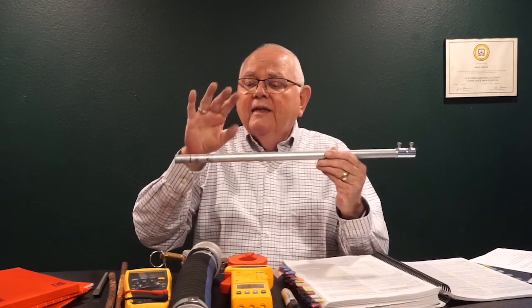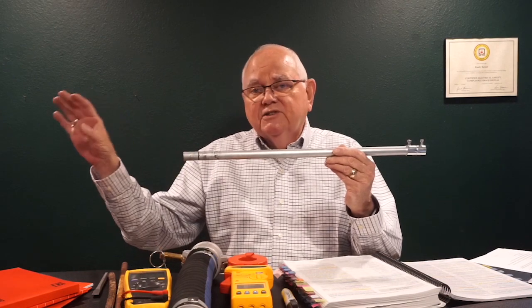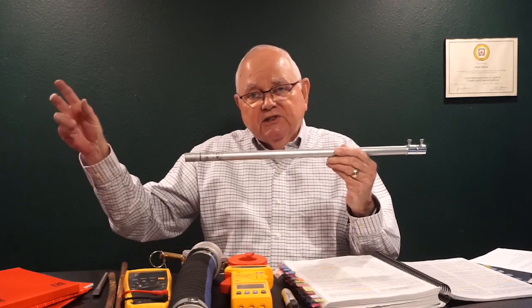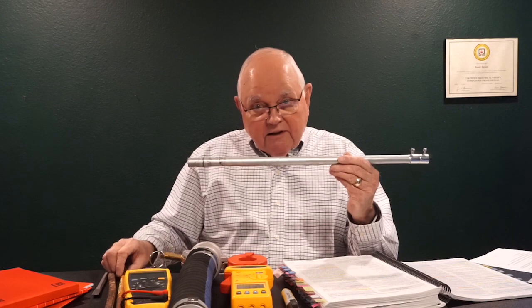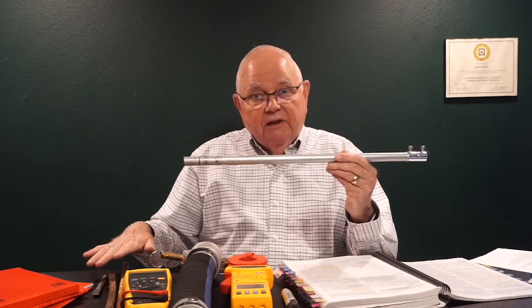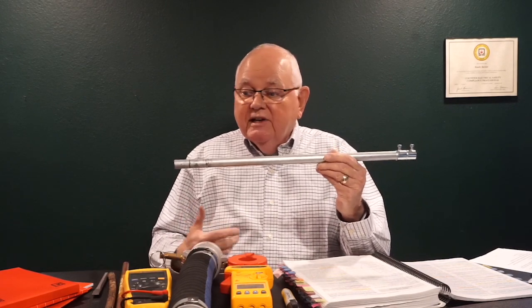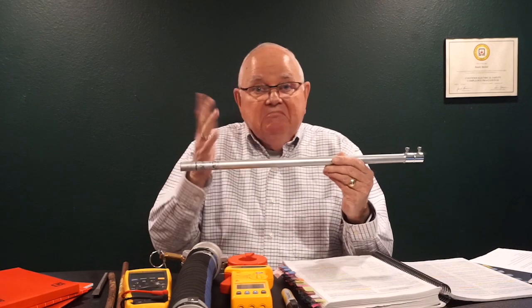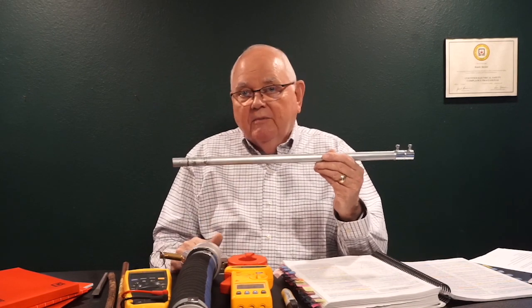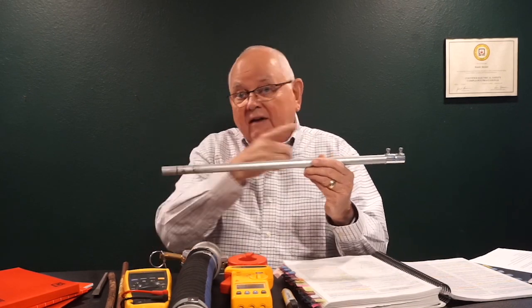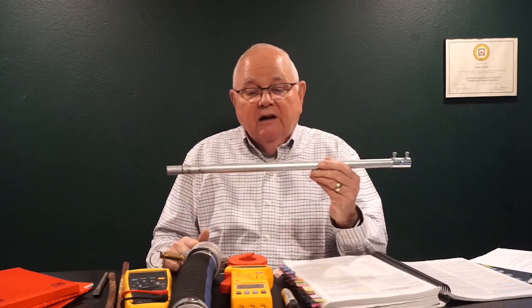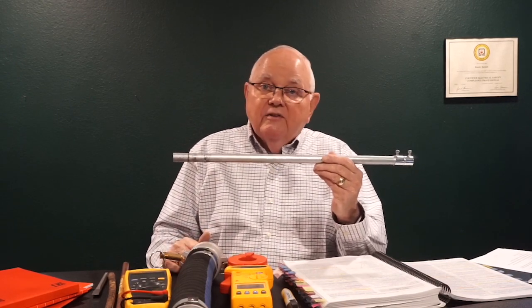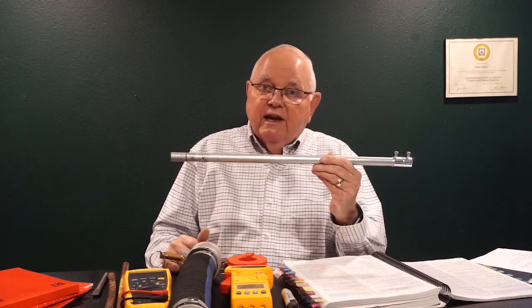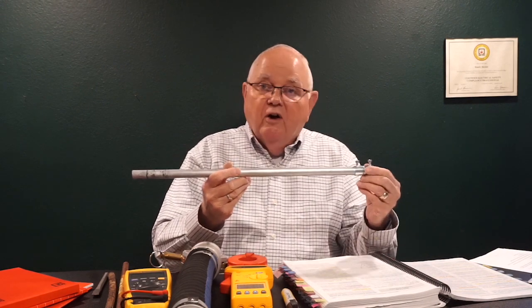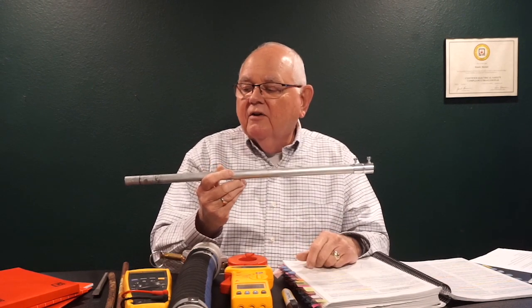so if this is connected all the way back to the source, which is in turn connected to the earth, right, through our grounding electrode system, then we're at the same potential. I'm standing on the earth. This is connected to the earth. There's no reason for current to flow through my body, right? And hopefully, however much current flows through this particular conduit is going to be enough to go back to the source and open or clear the fault by opening the circuit breaker or the fuse.